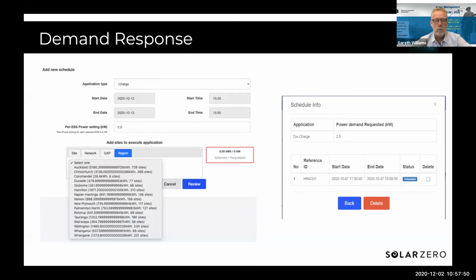Our system then allows us to set what do you want to do? Do you want to charge, or do you want to discharge? On what date and time do you want that instruction to last for, and how fast do you want the battery to do whatever you're telling it to do? So if we know it's likely to be a 4 or 5 hour event, then we would reduce the power setting to just 1 kilowatt, knowing that we're going to have adequate battery capacity to act right through that event.